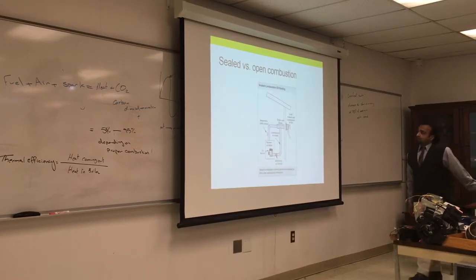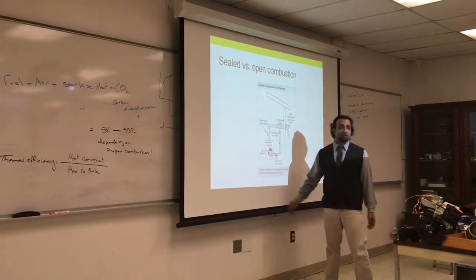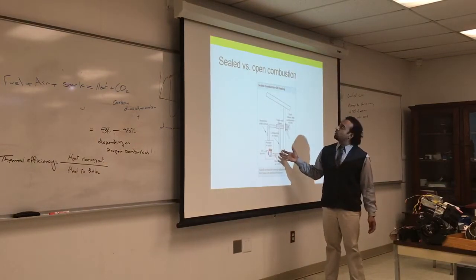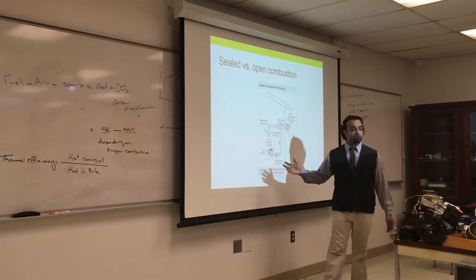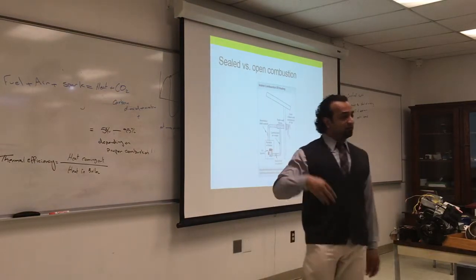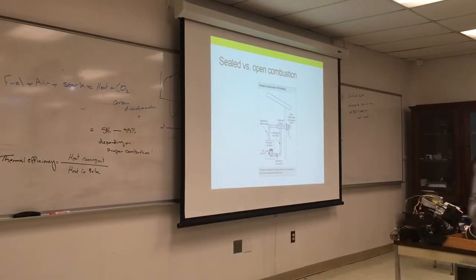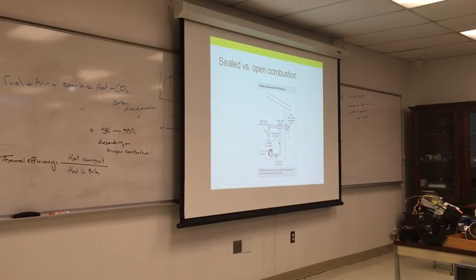Okay. Another concept I want you to think about thoroughly. It's very important. It's called sealed versus open combustion. What do we mean by that? So sealed combustion, you take the combustion air from the outside and you dump your exhaust outside. The house has no interaction with the combustion whatsoever, which is very good for people because they don't want to look at these things. They want to see a box that makes heat. They don't want to know why or how. So the open combustion, you pull the air from the house, from the basement, and you dump out the combustion air into the furnace. What is the problem?